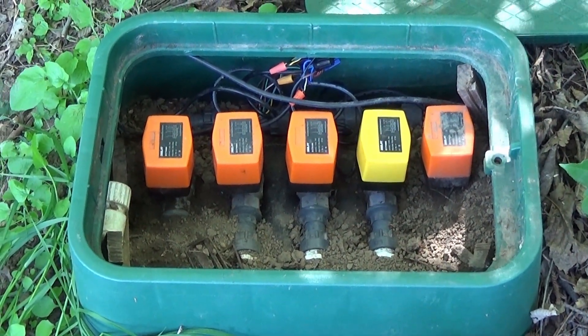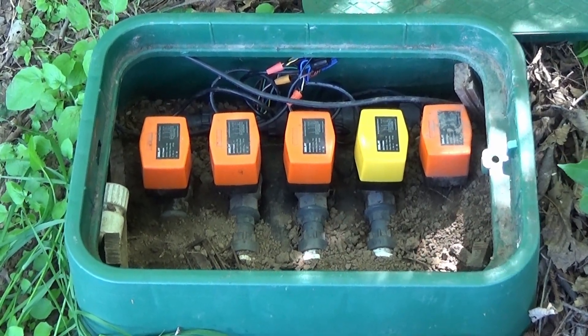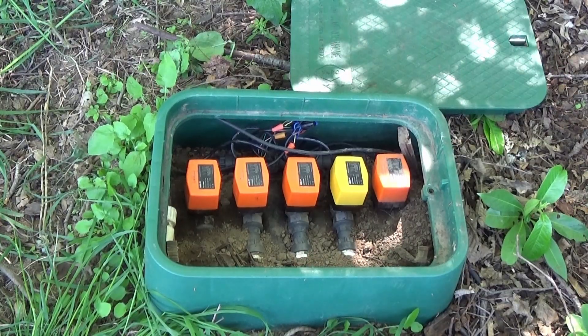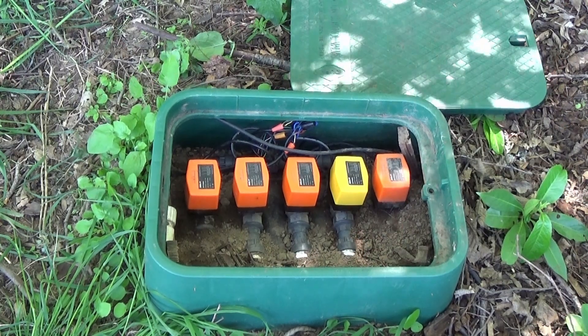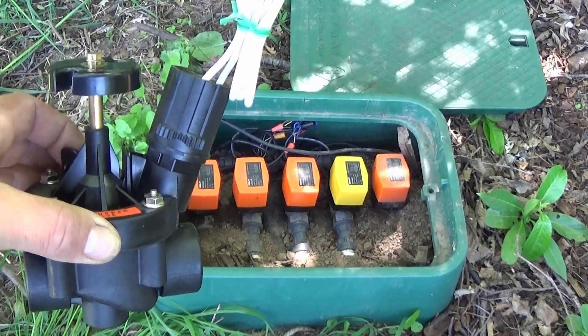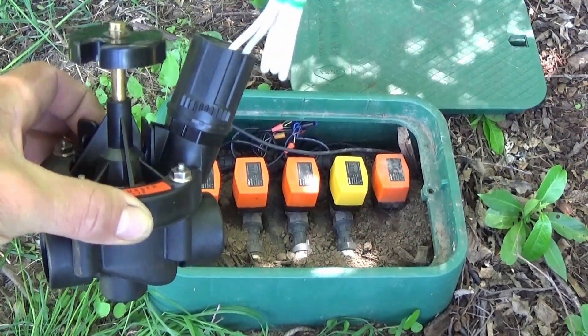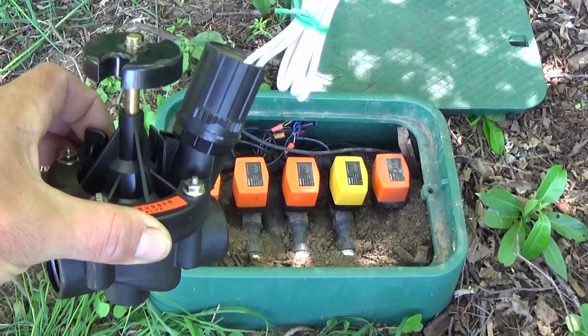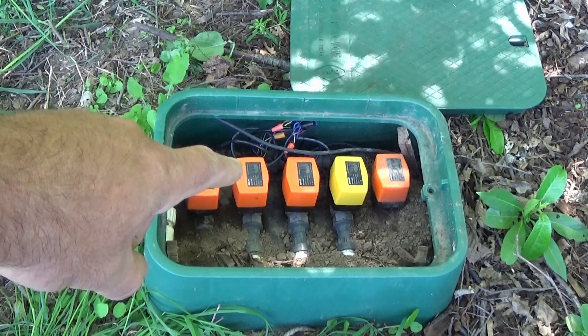A couple of reasons to use these things. The reason we're using them here is because we have very low pressure. This is a gravity fed system. We have about 5 feet of head — we hardly have any pressure at all. Nowhere near enough pressure to operate a typical solenoid valve or a sprinkler valve. Those need at least 10-20 PSI to operate reliably, or they won't open and close. The motor actuated ball valve will open and close on low pressure.